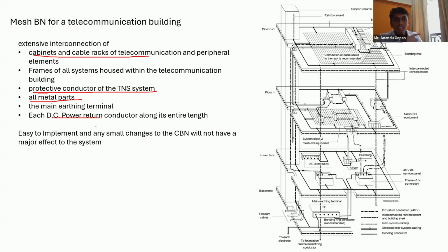So basically, at the start of this presentation, I told you that for DC you will have two things. One is called multiple DC connections, and the other is a single DC connection, the isolated DC connection. In this system, you are supposed to interconnect the DC return path along the conductor, so you are supposed to do multiple interconnections. So basically, I will go through this picture a little bit.